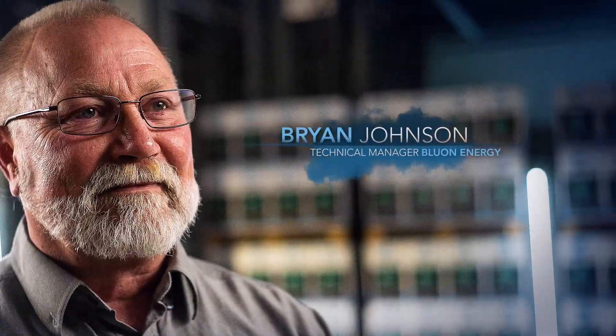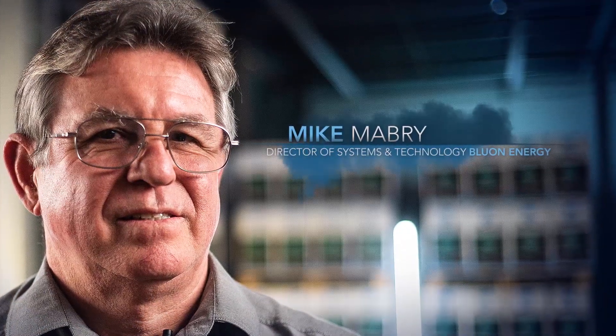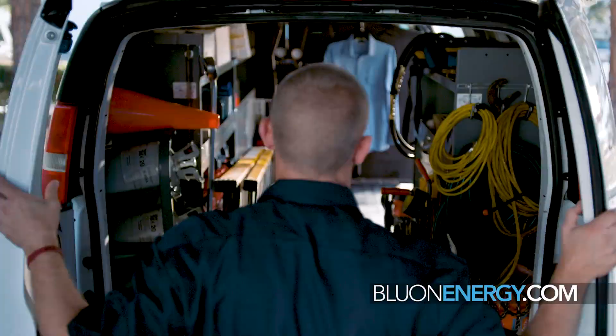With Bluon, we're doing things that were literally not possible before. Up on the roof in a condenser corral, we're at 130 degrees — the compressor's running cool, we're all screaming, 'This is awesome!' It was solid. The machine's quiet, the cooling is where it was supposed to be. It doesn't lose capacity, has better efficiency, and it's better for the equipment. I've never seen anything that works like this — R22 doesn't work like this.